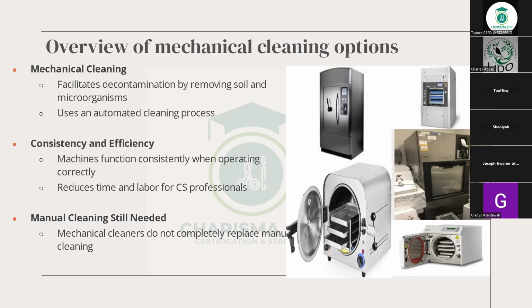However, when it comes to CSPD, the way we filter the water is that we have a whole system. There's a company called Avaqua. Avaqua will come install equipment in your facility where, before the water gets to your washers, it goes through that system where microbials, chemicals, and particulate contaminants are removed and reduced, and are completely removed. And some of the water will be pumped through the sink, through the cart washers, and also through the automated washers. To summarize, critical water is the water that meets all the specifications that are needed and recommended by the regulatory bodies for final cleaning. Thank you. All right, thank you, Director.